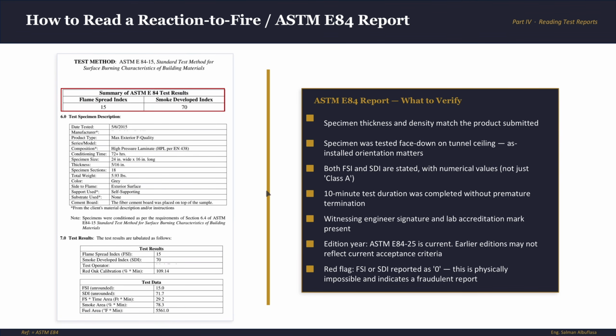That's number one. And then the specimen orientation. We've mentioned before that the Steiner tunnel mounts the specimen face down on the ceiling. If the orientation is different, then we need to verify what is wrong. And then both the flame spread index and the smoke development index must be stated with numerical values, the actual numbers. If you're comparing products and verifying the margin of compliance, you need those numbers. Class A tells you it passed; the number tells you by how much. As you can see here, flame spread index, FSI, is 15, and SDI, smoke development index, is 70. So you need to see the actual numbers of the data.